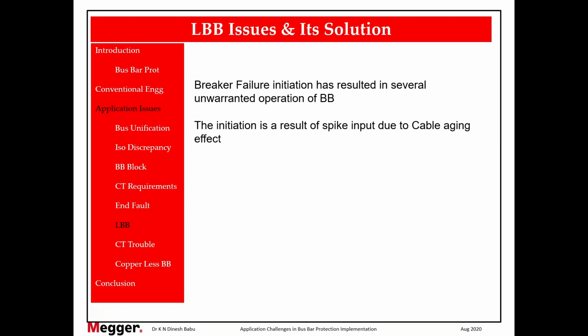So this is because of spike input due to cable aging, and the numerical relay input is very sensitive. When the input is sensitive, even if there is a 1 millisecond or 3 millisecond input high, breaker failure will immediately operate. Okay, how to solve this? Number 1, the breaker failure initiation signal should not be latched. It has to be self-reset. This is one common mistake in many numerical relay configurations. Self-reset or latched, you can choose anything. Numerical relays will permit anything, but we normally don't focus on this area. So we leave it as default, and by default, if it is in latch condition, even a 3 millisecond spike input will hold for another 200 milliseconds, and for those 200 milliseconds supervision current will anyway be available.